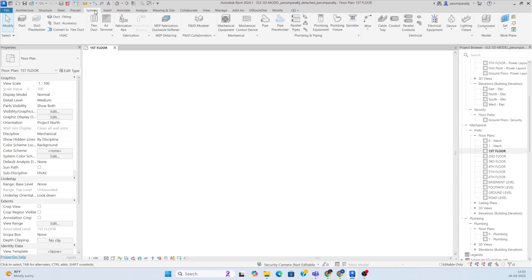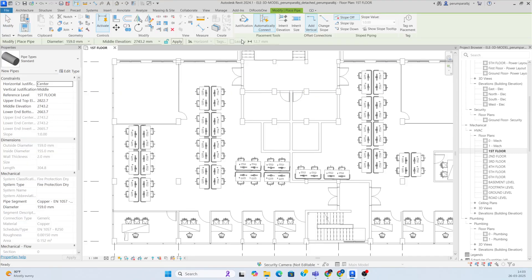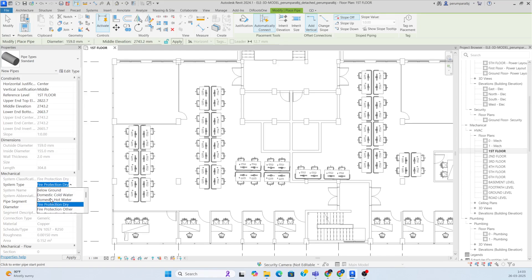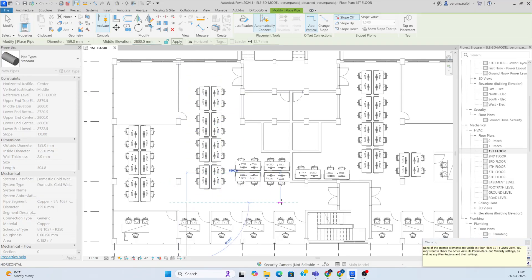Go to the system and draw some pipes. Go to the pipe tool, then choose which kind of pipe you need from the system types. For example, I'm using domestic cold water. From here you can choose the diameter for the pipe, then set the elevation — I'm giving 2800 — and draw the pipe.